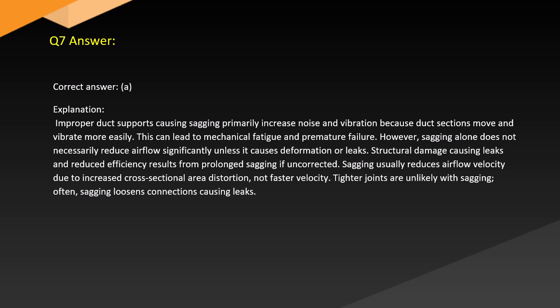Structural damage causing leaks and reduced efficiency results from prolonged sagging if uncorrected. Sagging usually reduces velocity due to increased cross-sectional area distortion, not faster velocity. Tighter joints are unlikely with sagging. Often, sagging loosens connections causing leaks.